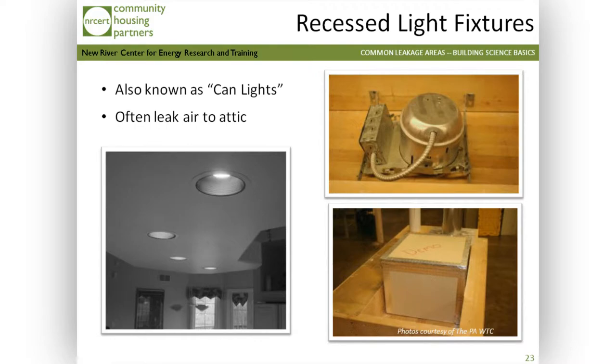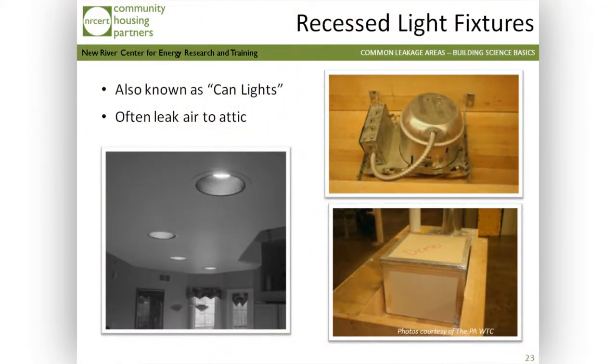Seal the hole. Now, can you use can lights that don't have holes in them? They're IC cans without the holes in them. Even an IC can has some holes, but you're right. There are better can lights than others. Aren't there sealed can lights available? Yeah, that's what I'm talking about. There are airlock and airtight cans, and they do pretty good, yes. Halo makes different brands, but they're still not completely airtight. They're just little punch outs and things like that. They're less than 2 CFM, I think at 75 pascals of pressure difference across the surface. So for them, it's considered to be airtight. That's their definition of airtight.